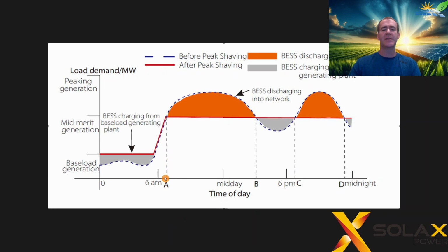Now these are the default times that are set up in your settings. So you can see from 11 o'clock till 7 o'clock is off peak, and then 7 o'clock until 3 o'clock is peak, and 3 o'clock till 7 o'clock is off peak, and then 7 o'clock till 11 o'clock again is peak. And so the idea is, in an off peak period, energy is stored up in the battery and ready for the peak period. Now, when your power usage becomes higher than a threshold set by the energy company and they start to charge more money, the battery and the solar then take over running the house load. And essentially it shaves the peak off at the limit that you set.